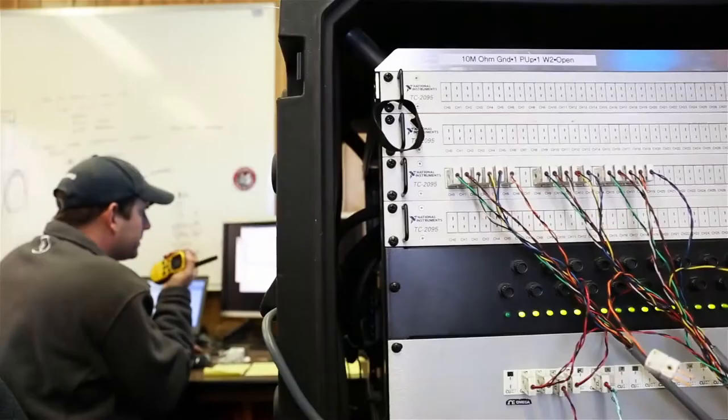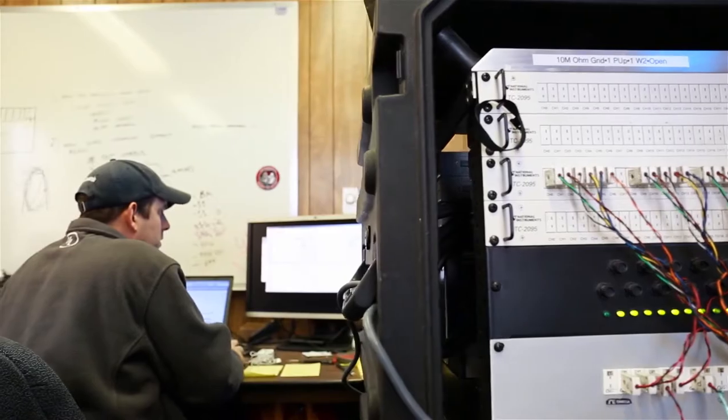Today we're measuring airflow through the use of bidirectional probes. Our probes are connected to a pressure transducer, which takes a pressure signal and changes it into an electrical signal, which runs back to our data system. We're using 5 different probes today at 2 different ranges to try and determine the total airflow that's moved by the nozzle.